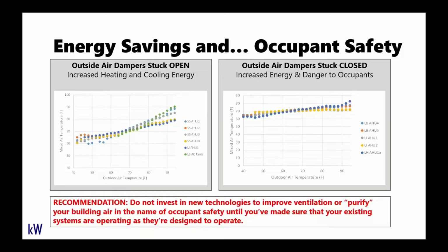Now, in terms of ventilation, that's great. That's maximum fresh air for the occupants. But once you start getting up into these 80, 90 degree ranges, it's very likely that your cooling system is not designed for that type of outdoor air temperature at 100% outside air flow. And as a result, it's likely that your zones are not going to be able to maintain their temperature set points. And similarly, at the low end down here, once we get down into the 40s and below, bringing in 100% outside air is going to make it impossible to keep those spaces warm in these temperature ranges. So there's an issue with maintaining heating and cooling set points, and there's a large burden on the energy consumption of the heating and cooling systems as a result.